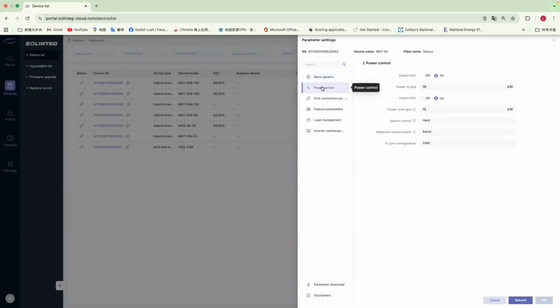Next, let's move to the power control. From here, we can set the export limit. If we turn off this limit, as we mentioned before, the power export will follow the capability of this inverter's AC output power. If we turn on this function, we can send the power to the grid. We can also choose to turn the import limit off or on here. This is mainly related to the contract with the grid operator and also to the main breaker installed inside our house. We can also set the value of power from the grid here.